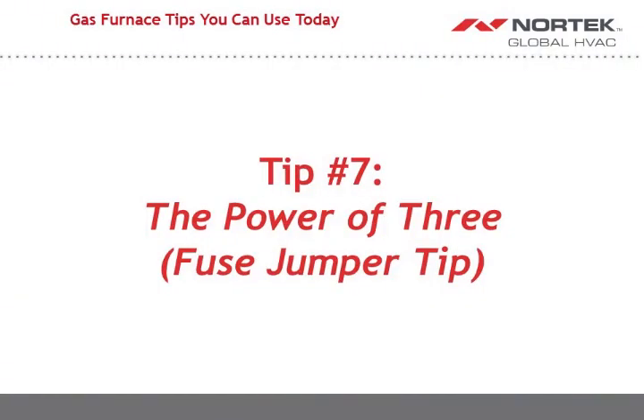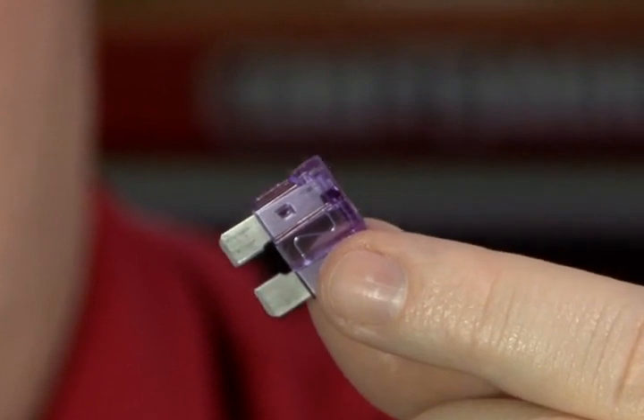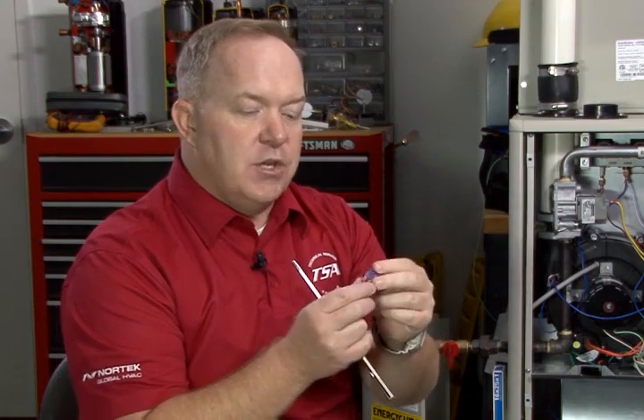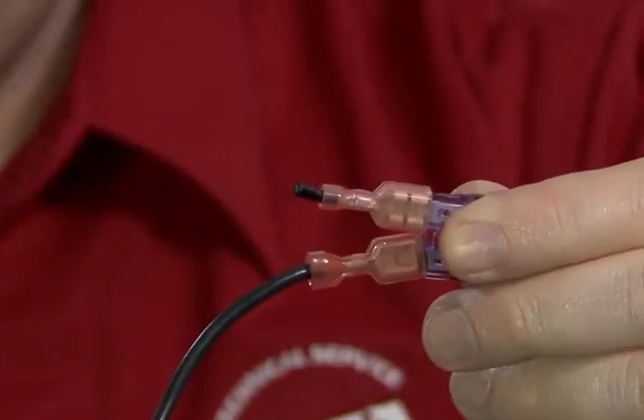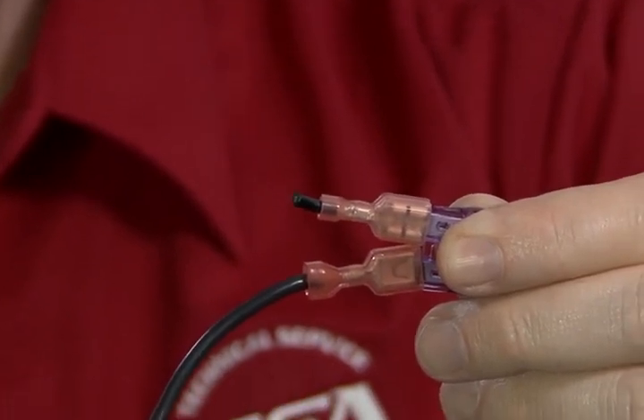Tip number 7, I like to call the power of 3. Something as simple as a 3 amp blade type fuse like this is, as simple as it may seem, very effective and very useful to act as a jumper when you need to connect two of the female spade connections. Let's say you are trying to effectively jump out a pressure switch circuit for troubleshooting. These come in awfully handy for doing more than just acting as fuse protection on a board. They act as a jumper between the female spade connections of the ends of two wires in a particular control circuit.